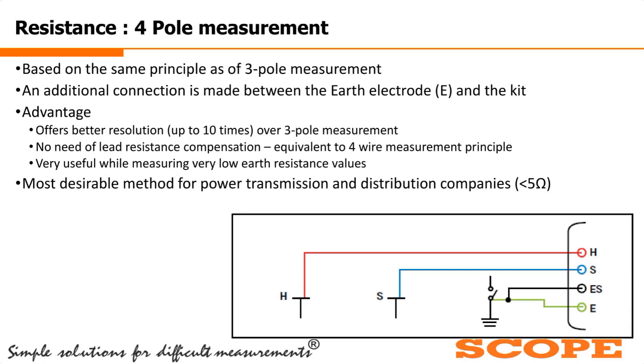So with the help of this four-wire measurement principle, the four-pole measurement method gives us a better resolution as compared to the three-pole measurement method. This method is widely used for earth resistance measurement in power transmission and distribution companies. Generally, the four-pole measurement method is the one widely used.